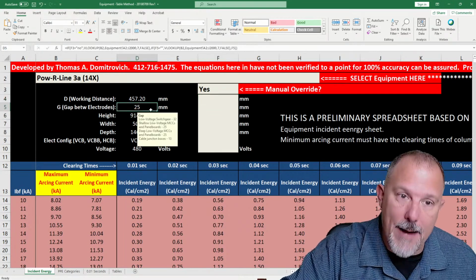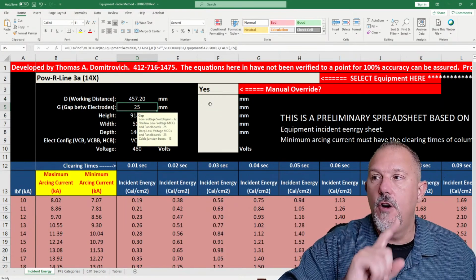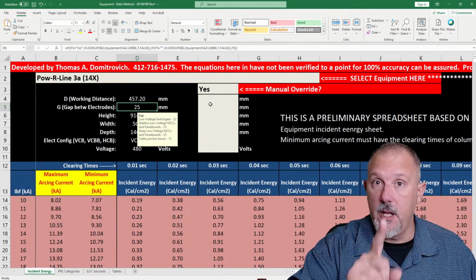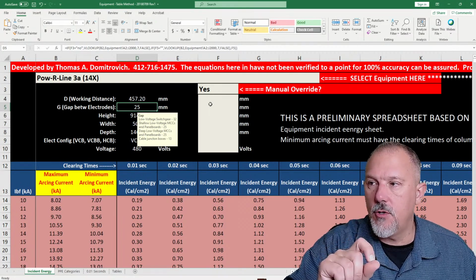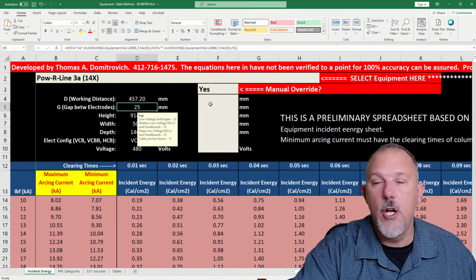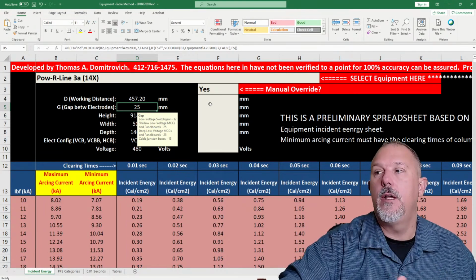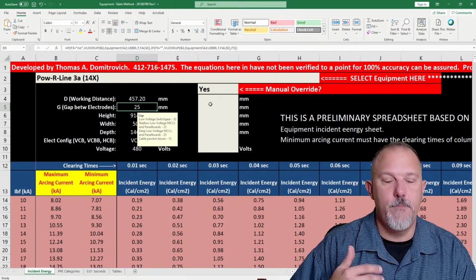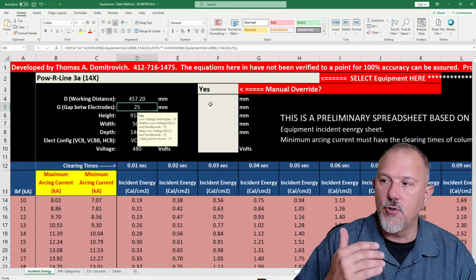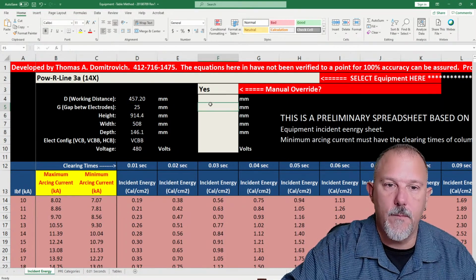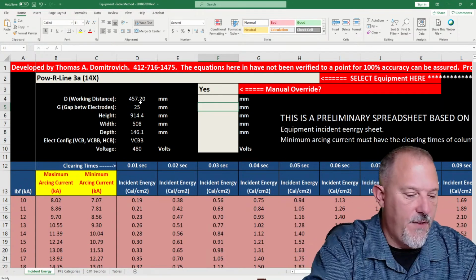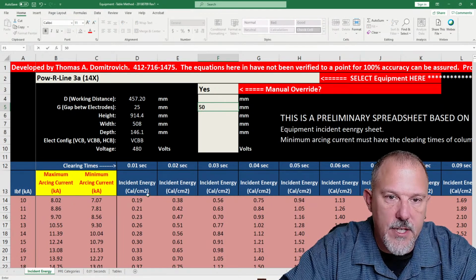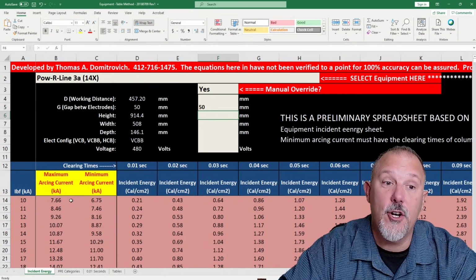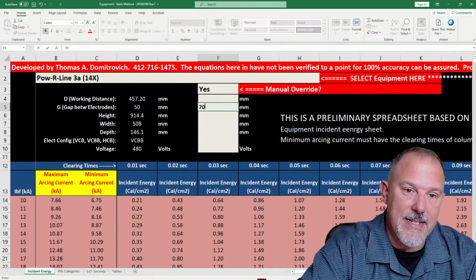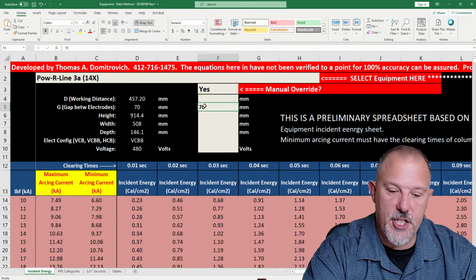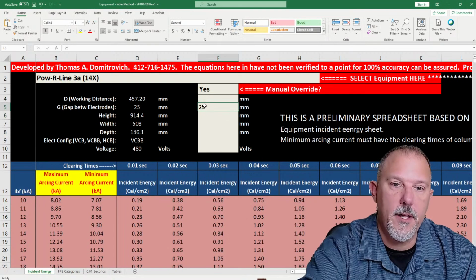So how about the gap between electrodes? What do we know? For low voltage switchgear, the gap is 32 millimeters. For shallow low voltage motor control centers and panel boards, 25 millimeters. Deep low voltage MCCs and panel boards, 25 millimeters. And cable junction boxes, 13 millimeters. So if I take the 25 millimeters and double it to 50, watch the arcing currents and watch the energy. My arcing currents changed. If I make it 70, my arcing currents changed. If I make it 25 again, my arcing currents changed.